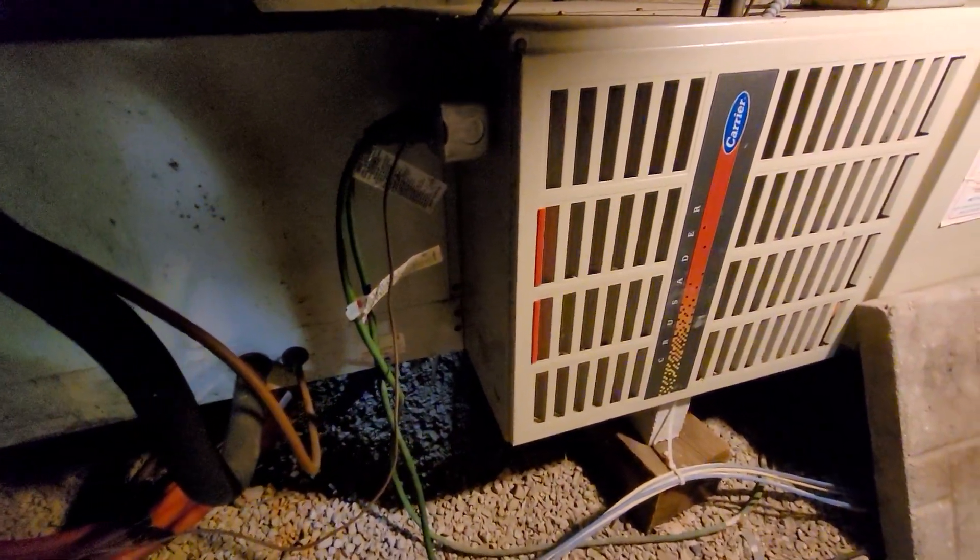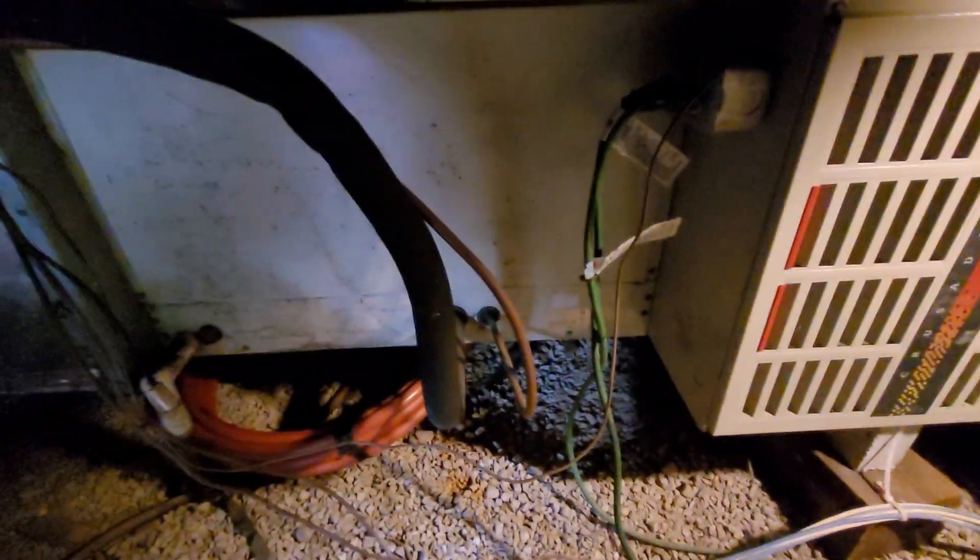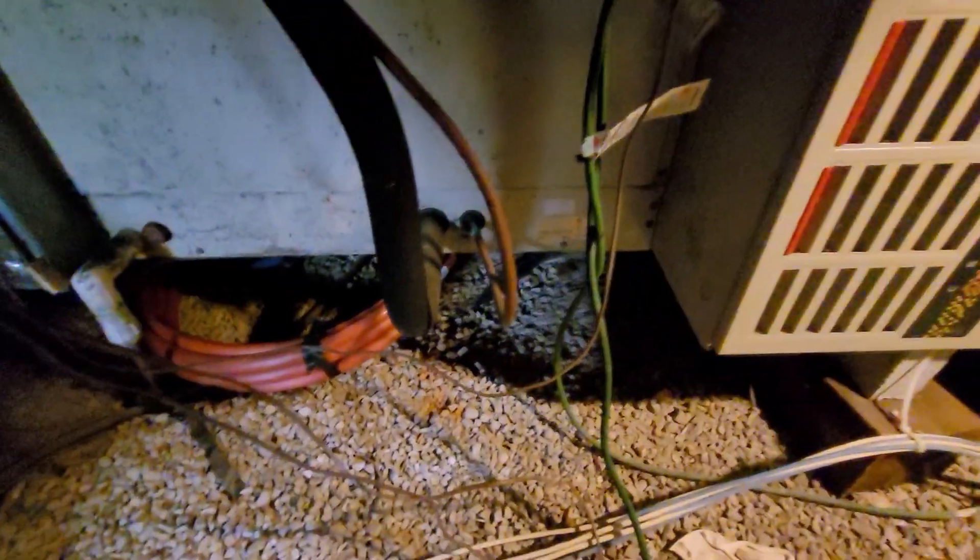The joists do run opposite, but you can see that we're able to fit a 4-inch floor vent as well as a sump pump vent out that wall, so we should be able to fit a 2-inch PVC line from there. We've got a horizontal AC coil that is a 3-ton right now, and that is draining over to a pump.